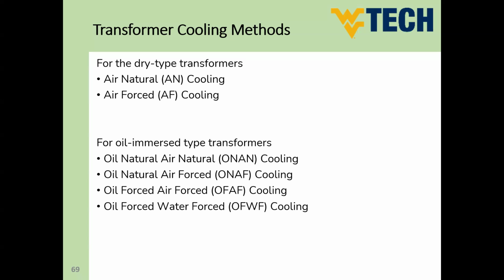So we can have what's called a dry type transformer. Dry type means it has no fluid inside for cooling. So we have no fluid, just air. So this is called dry type transformers. Actually, dry type can be found for low rating transformers. So you cannot find it in like several tens or hundreds of megavolt ampere. It's impossible to find this with a dry transformer, but you can find it in several megavolt ampere transformers.